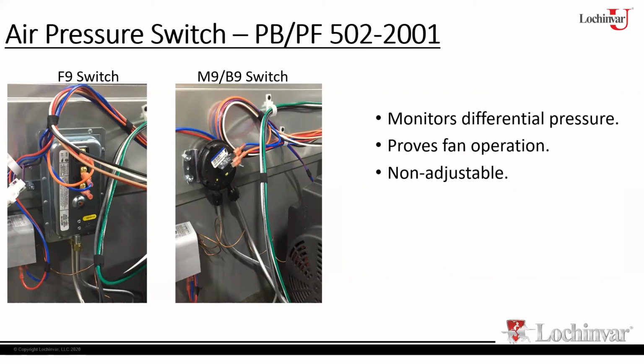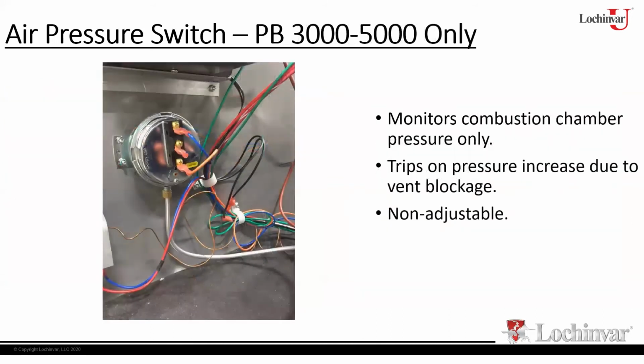That's all. Now, the larger models, the 2.5 to 5 million, when you look at it, get a different switch. It gets a single pressure switch because, again, neg-reg, this is a normally closed set of contacts on this switch. So if the pressure inside the combustion chamber goes up, the contacts will open and the unit shuts off. But you notice it says up there 3 million to 5 million only. Why doesn't the 2.5 get one?